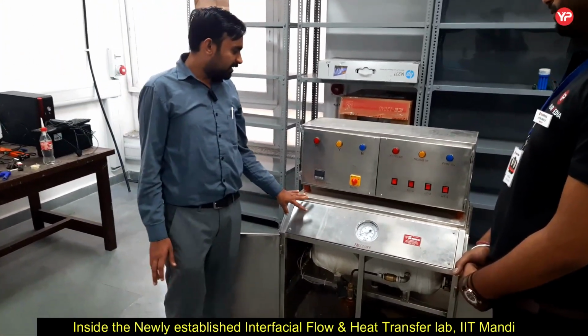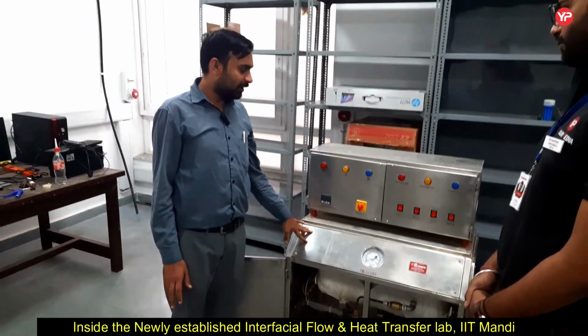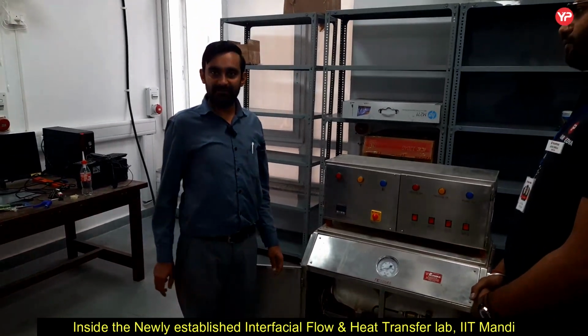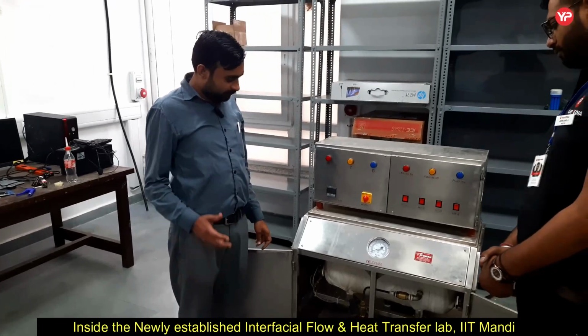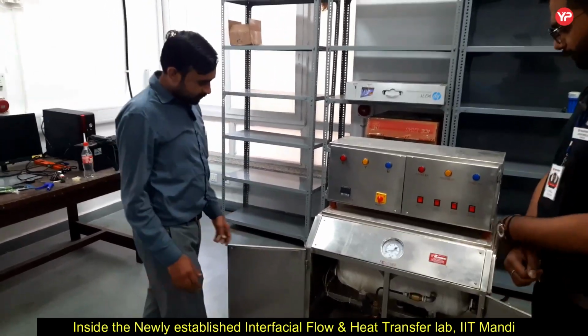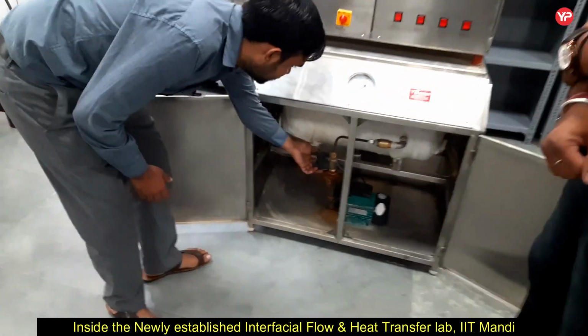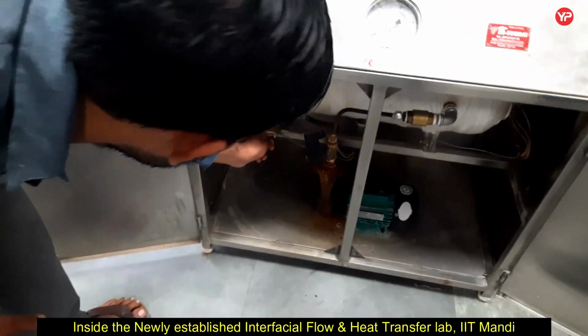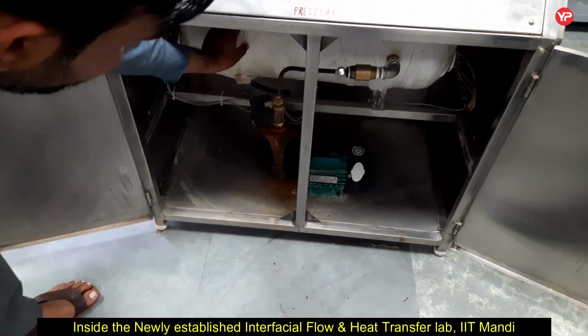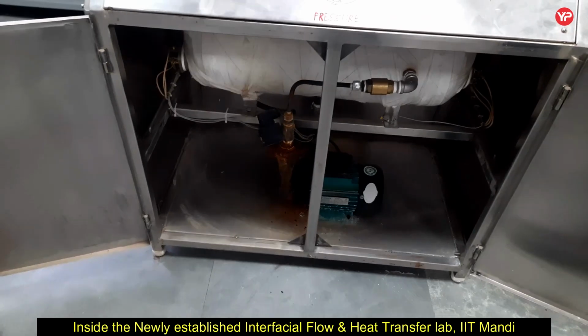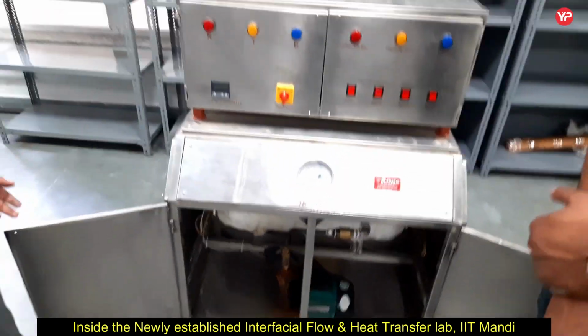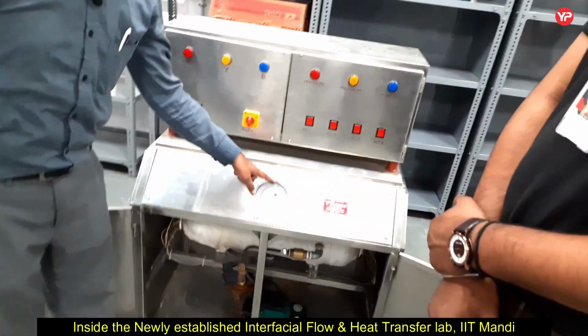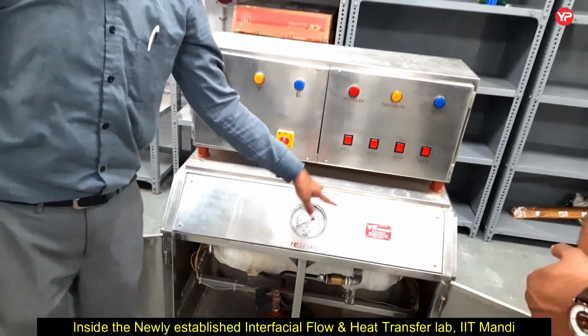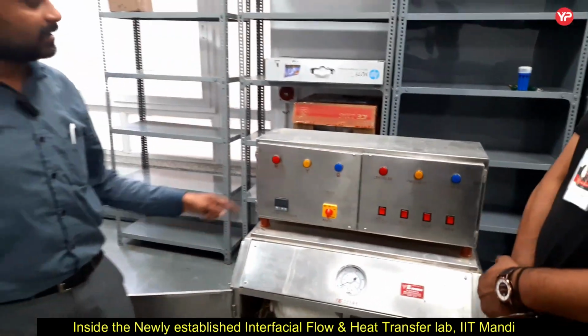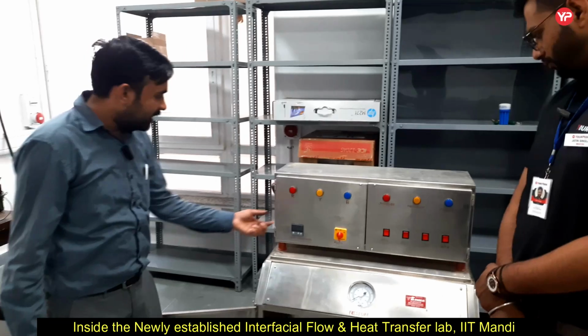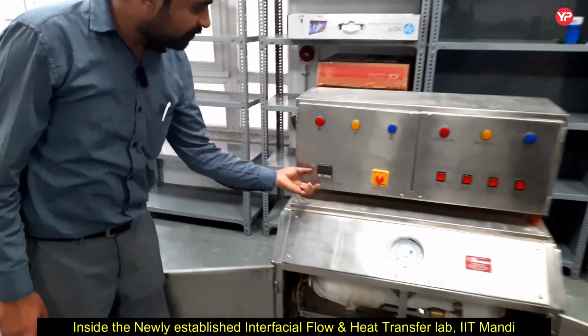Now this particular boiler has two main important safety features. The first is a pressure switch over here. This pressure switch avoids any overpressure within the boiler drum. If pressure goes beyond the set limit of 5 bar, this pressure switch will automatically switch off the heater.